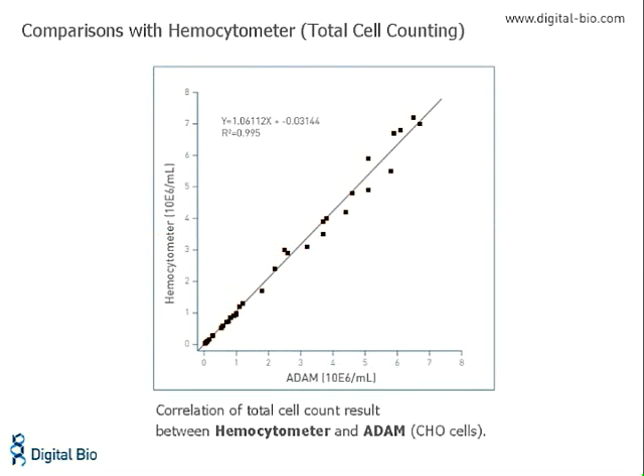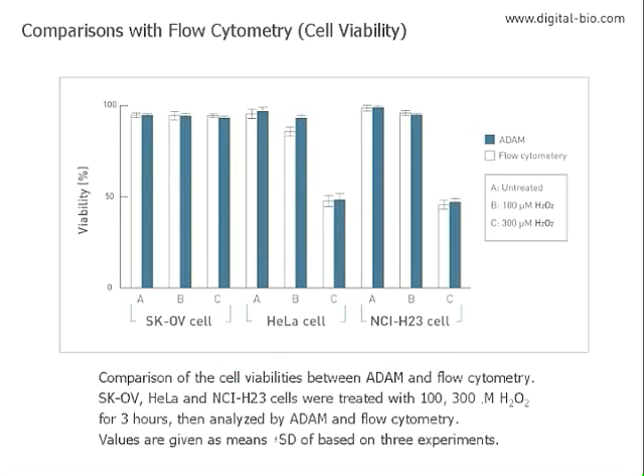ADAM compares very well with traditional counting methods using a hemocytometer. A comparison of ADAM and hemocytometer-counted CHO cells is demonstrated in this figure. ADAM also measures up against flow cytometry as a platform for determining cell viability. In the following experiment, cells from each of three cell lines were treated with two different concentrations of hydrogen peroxide at toxic and subtoxic levels. SKOV cells show a higher tolerance of hydrogen peroxide than the HeLa or NCI H23 cells. Results obtained with a flow cytometer are accurately reproduced by ADAM.